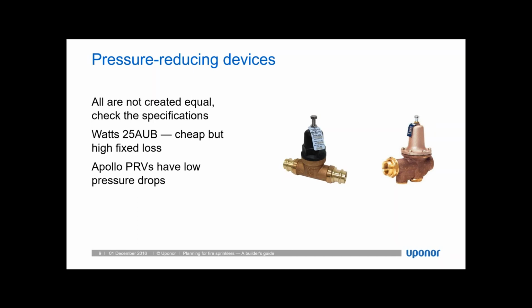However, we would never recommend a 3/4 inch pressure reducing valve. It may be more anecdotal than anything else, but I have not seen many 3/4 inch pressure reducing valves that are capable of flowing what is required for a sprinkler system. And we're able to verify this because we always recommend that your residential sprinkler system be flow tested. And we have not seen that flow test pass anytime smaller than a 1-inch pressure reducing valve has been used.